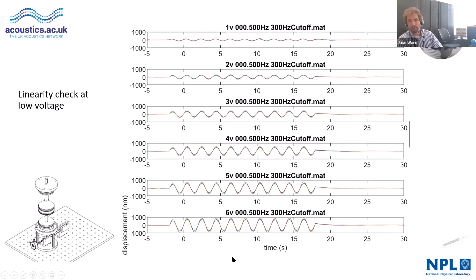So the quadrature interferometer, I have enjoyed working with lasers. It's very much as fun as it sounds. And I liken this quadrature interferometer to a corkscrew. If we have two orthogonal beams of light or interferometers, then we have a sine channel and a cos channel, and each fringe of light is like a rotation of the corkscrew. And we can accumulate the phase, so from the phase of the interferometer we can infer the displacement to sub wavelength. The wavelength of light we're using is red. It's 630 nanometers, and so each fringe is half that, 300 nanometers ish, and we can get down to about 30 nanometers accuracy with the noise on the electronics.